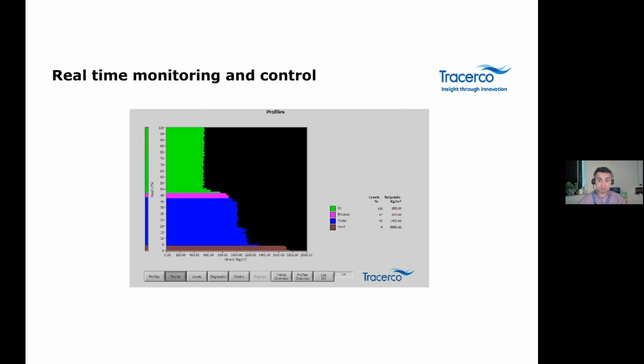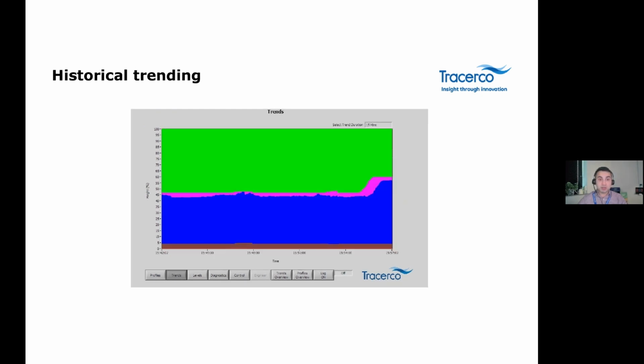The HMI offers easy access to process and instrument status in real time, as well as the trend data, allowing adjustments to the process to be monitored and changed on the run online, enabling decisions to be made faster, analysis easier to understand, and a greater depth of optimization. The instrument can now be fully integrated in the client's DCS. That's also one of the optional parts.